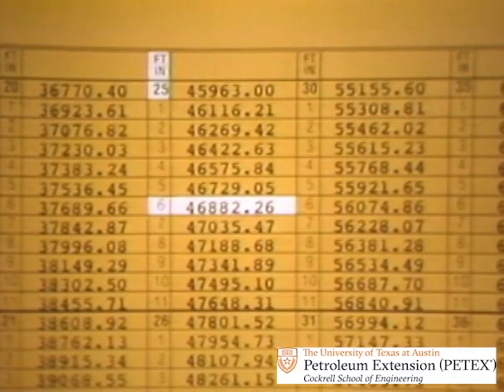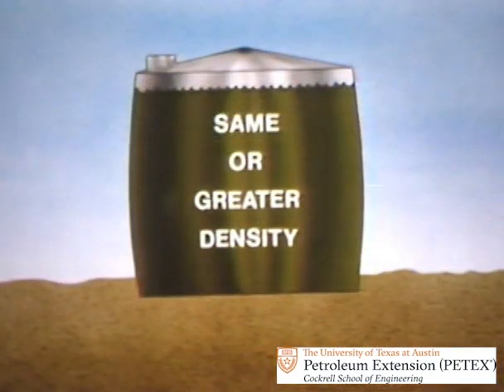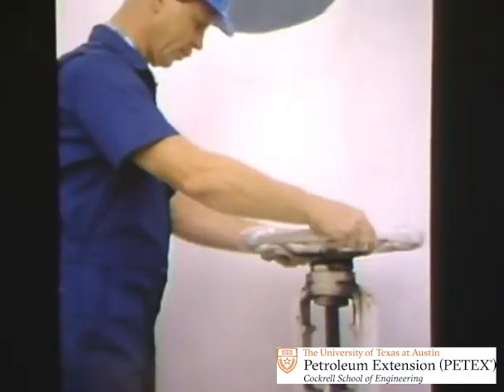The purpose of tank calibration is to allow the development of accurate capacity tables. Tables to show you the amount of liquid in a tank at any given height. Before a crew starts strapping, the tank must have been filled at least once with liquid that's the same or greater density than the liquid normally in the tank. All inlets and outlets on the tank must be closed, and no liquid can be moved in or out of it.